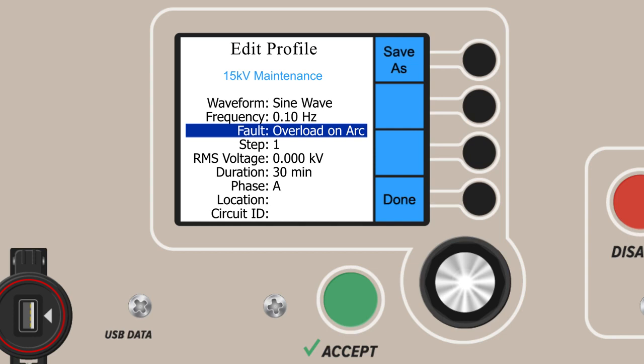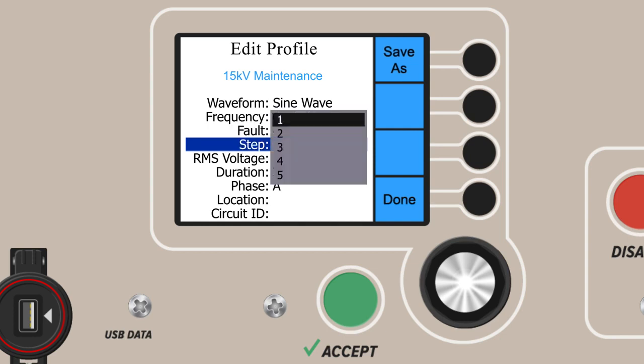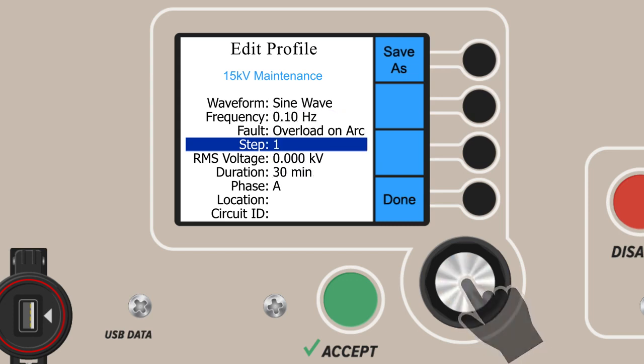The next parameter is Step Selection. VLF E-Series are programmable up to 5 steps. Some tests may require just a single step of testing. Others, such as a tan delta test, require 3. By default, our first step is Step 1. Should we add extra steps, we come back to this menu and choose a second or a third step. The other parameters won't automatically clear, but they become editable again. You can then change parameters such as voltage or time by using the same controls as earlier.